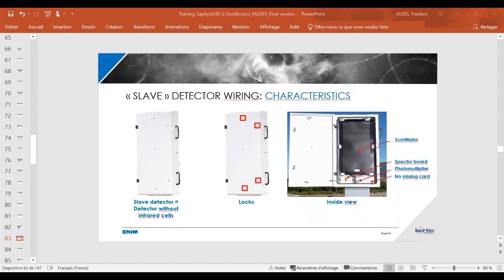Now concerning the slave detector, easily identified, of course, since you have cabled the master detector. Just as a reminder, this is a detector without infrared cells, and inside the detector, you only have the scintillator, the photomultiplier and the spectral board. No mixing card. The mixing card is only on the master detector.